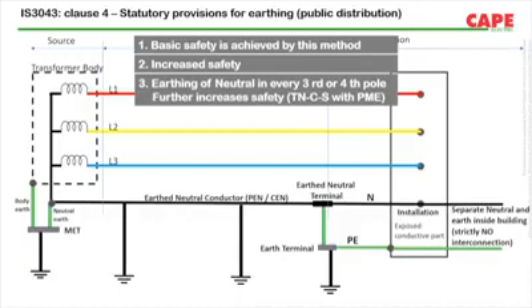Suppose a line conductor accidentally falls in soil. There is a fault return through the earth electrodes of the PME system. This fault current through neutral can be detected and the supply can be disconnected. This PME system also reduces the overvoltage dangers during neutral disconnection.